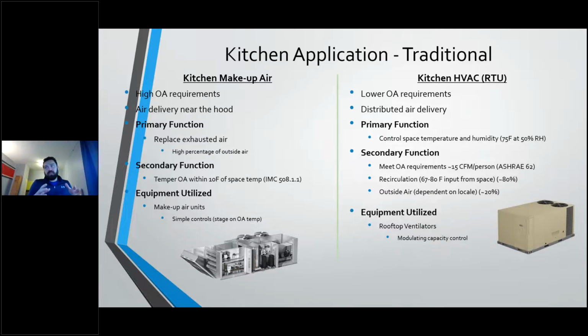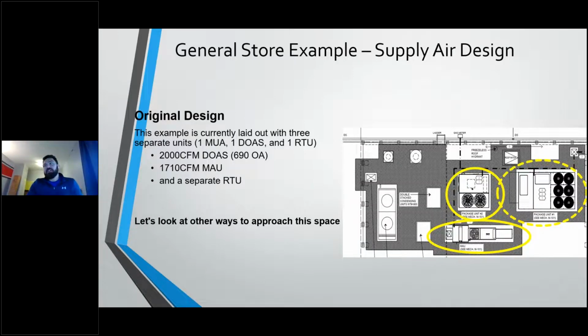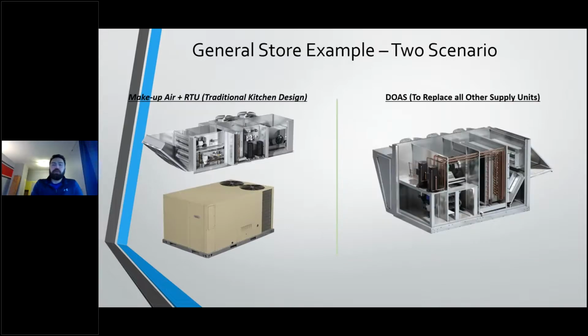So that's the traditional, and I think what I have been seeing is that in smaller footprint, I'm jumping ahead of myself. So I said we're going to look at 3 different designs, and we are, very quickly. First design is just a general store. Now, this original design was utilizing a DOAS unit, still utilizing a makeup air unit with direct fired makeup air and cooling, and then a rooftop unit, which is fine. Nothing inherently wrong with this. It works. It replaces your outside air. It's slightly dehumidifying. But how else can we do this? And we can do it in two different ways. We could do it with the traditional kitchen design of that makeup air unit with DX cooling and a rooftop unit, or we can do it with a DOAS system.